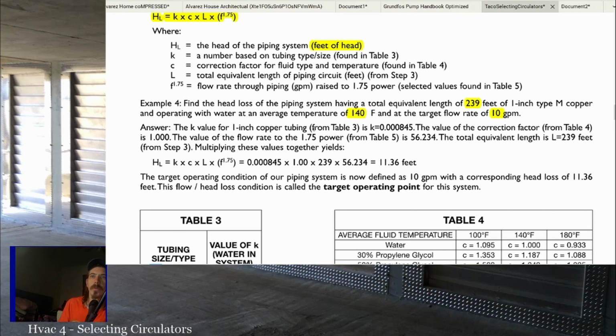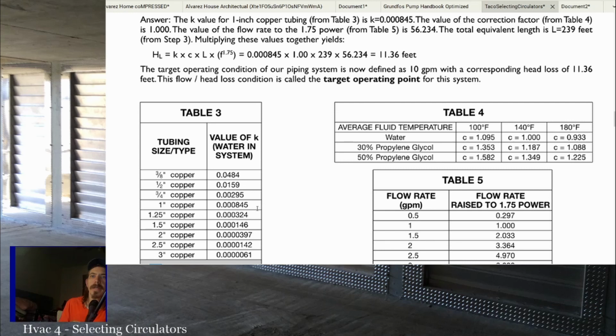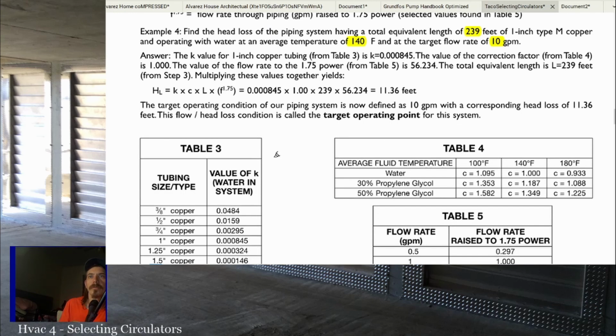So the K value for 1-inch copper from table 3, you just take this value and plug that in for K, is 0.000845. So you plug that in here. The correction factor from table 4 is 1. So 1 is our baseline, basically, right? They base all these numbers off of a standard density of water at 140 degrees as our 1, and then as the temperature changes, it goes up or down from that. Anything is going to have some kind of baseline for its density, and they're using that as the baseline in this formula. So that would be 1. 239 is our equivalent feet, and 56.234 is 10 to the 1.75 power. So you multiply all those, and that's 11.36 feet of head.